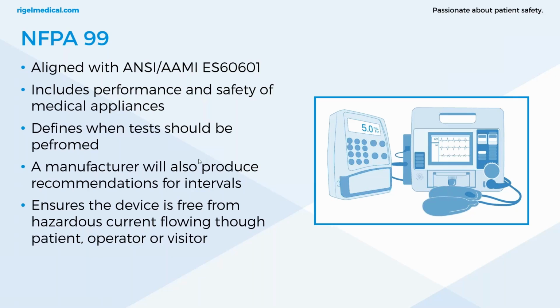In some of the previous revisions of NFPA 99 that I've looked at, there have been statements of 6 months in critical areas and at least every 12 months for general areas. Now, I've noticed in the latest revisions that these statements are starting to be phased out, but the risk there is still present. So they're still good guidelines to follow, even though they have been phased out of the standard. The regular testing just ensures that the medical device is free from any hazards.